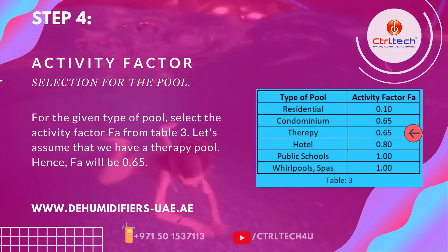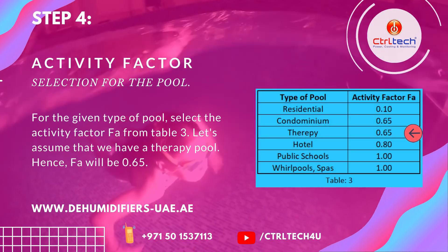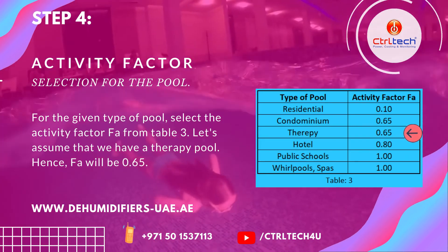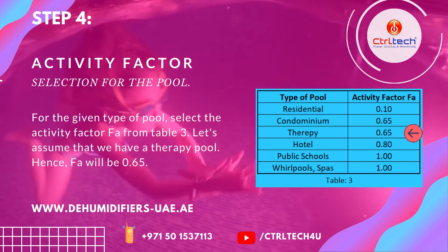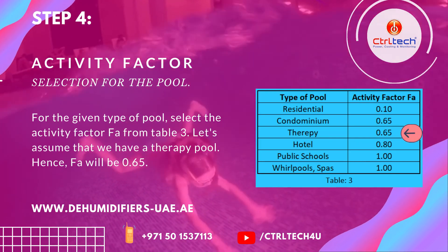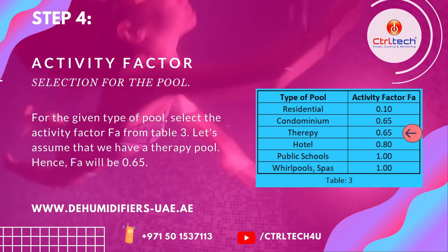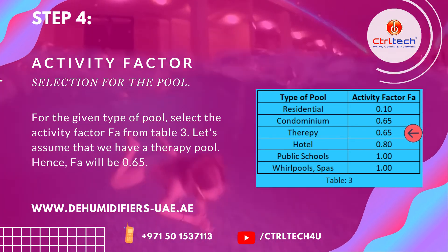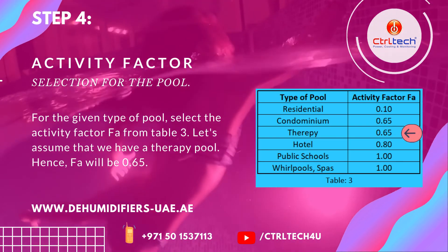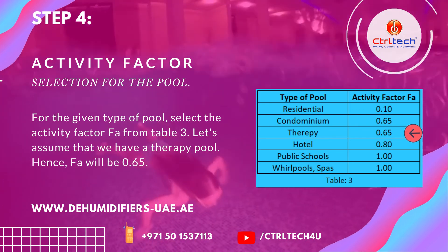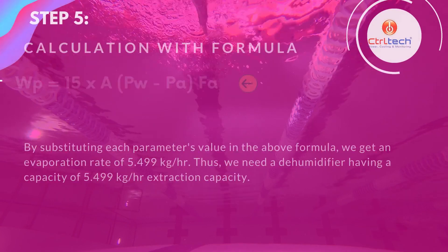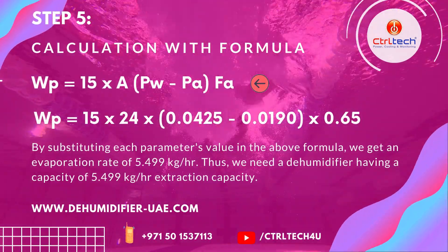The evaporation rate also depends on the number of people using the swimming pool and hours of usage. For example, the evaporation rate will be more for a public pool which is always occupied than a private pool. This phenomenon is factored into the dehumidification load calculation formula with the help of the activity factor. For the given type of pool, select the activity factor FA from Table 3. Let's assume that we have a therapy pool, hence FA will be 0.65.